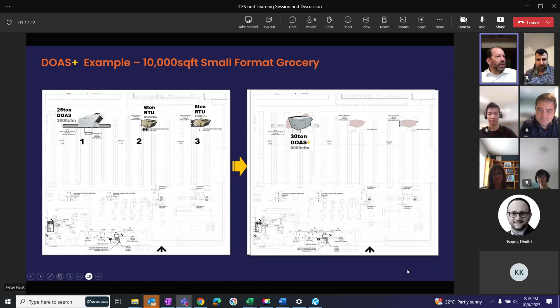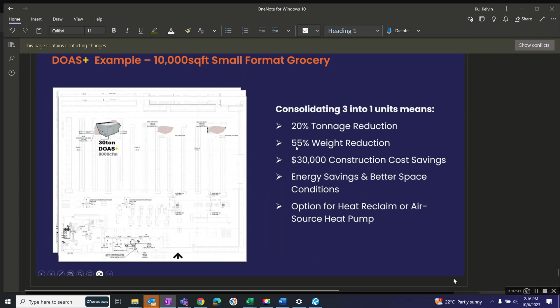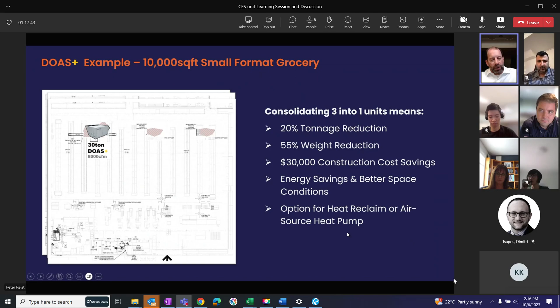Here's the savings: 20% tonnage reduction, 55% weight reduction when you consolidate all those units. In this project, it would save them $30,000 in construction labor - all the hookups, the electrical, piping, natural gas. We get better space conditions, and have the option for heat reclaim and air source heat pump, or in your case, water source heat pump. So it really gives a lot of opportunity there - just a very simple example.